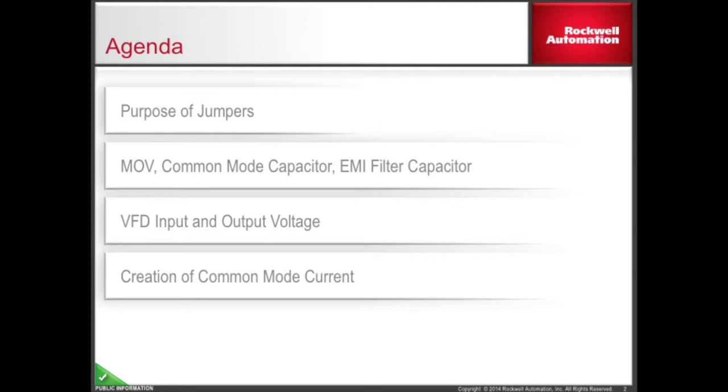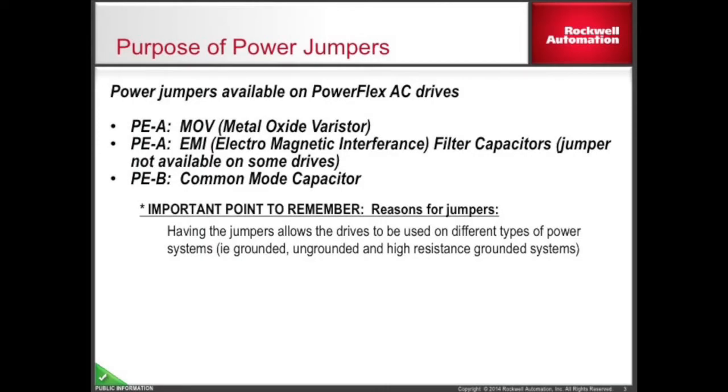A link is provided in the description, which provides documentation showing all of the PowerFlex 750 drives, their frame sizes, and jumper locations. All of the PowerFlex 7-class drives are provided with power jumpers. Having these jumpers allows the drives to be installed on any three-phase AC power system. Installation of the jumpers provides a path to ground for their associated device.